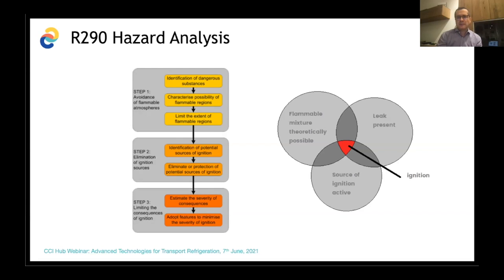In order to have a flammable mixture, which today in supermarkets you have, propane is already installed. And this means that if you're running with the cleaning machine in the supermarket, this can happen, right? But in transport refrigeration it is still a big issue. And we also have isobutane in our cabinets and commercial household refrigerators in each home of ours. Since the low charge is given there, and we succeeded also with the low charge in transport refrigeration, and we've done our homework on the hazard management and risk management of flammability, we came to a likelihood of 10 to the minus 9. That means that we'd have to sell 1 billion units for it to happen.